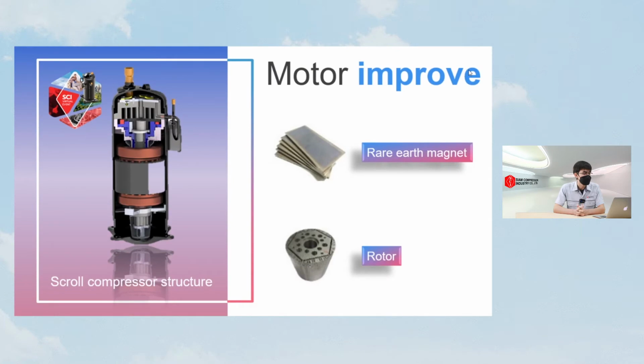With the motor improvement, our new motor design contributes to a higher APF level. Our new motor is made with rare earth magnets inside that provide a higher motor efficiency. Generally, scroll compressor components consist of very high precision parts. If we look deeply into the compression part, the fixed and orbiting scroll, the clearance between the tips of the scroll can cause leakage in the compressing process, which leads to lower efficiency. So with the clearance matching technique, we match the fixed and orbiting scroll to form a smaller gap so the scroll compressor can get higher efficiency. We get 3% more in very low temperature conditions, and 5% more in normal cold temperature.